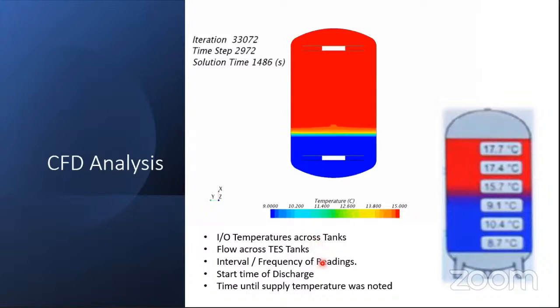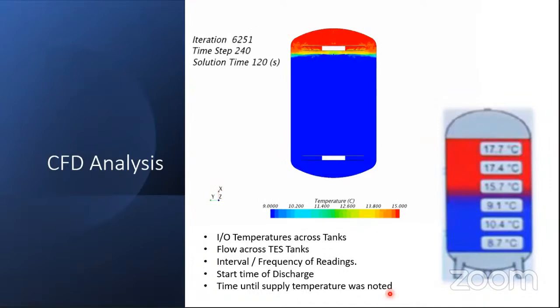These parameters are noted. The start time of discharge is also noted, that is, when the discharge started at the desired temperature, and the time until the supply temperature was maintained was noted. For example, if I were to draw a 9-degree supply temperature, I should be getting the 9 degree. Anything above 9 degree, my time has ended. So that is also recorded to measure the time duration of the backup which has been planned.